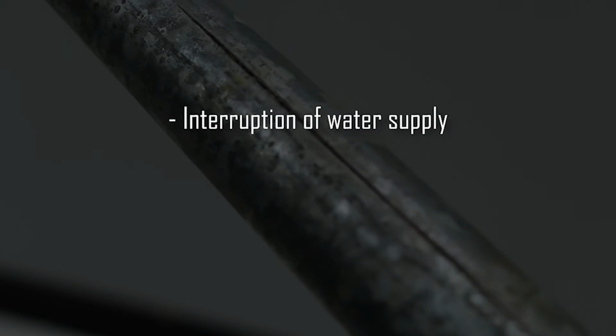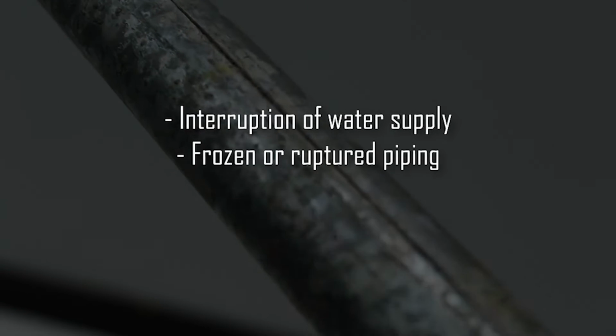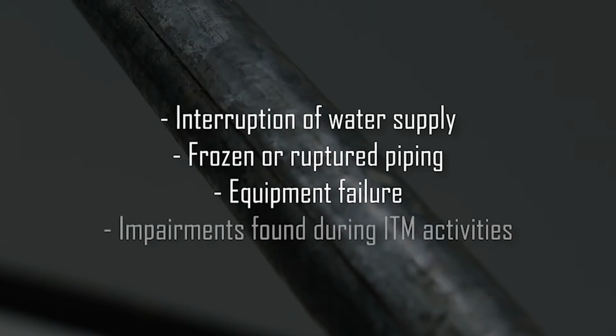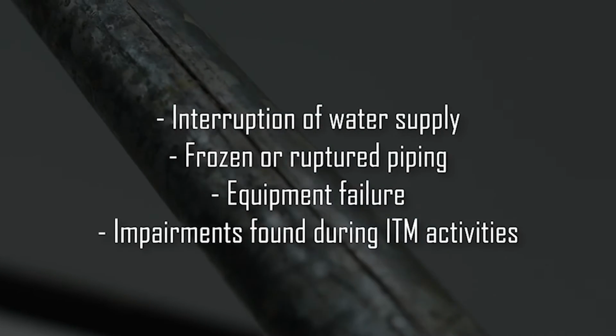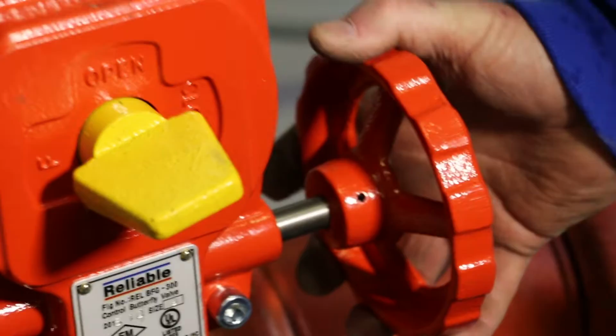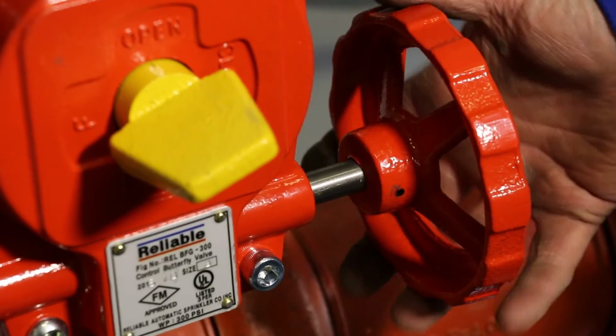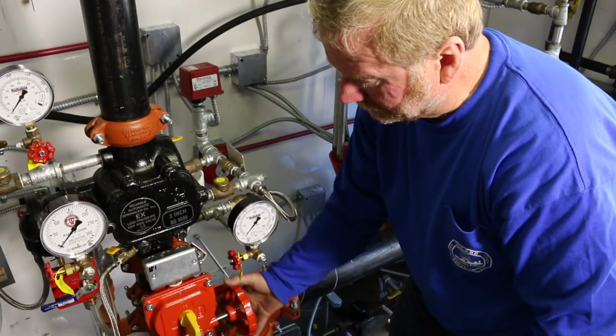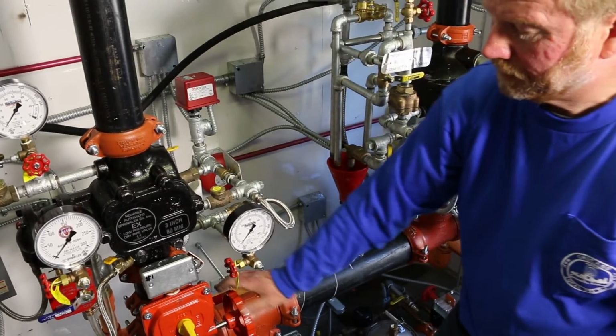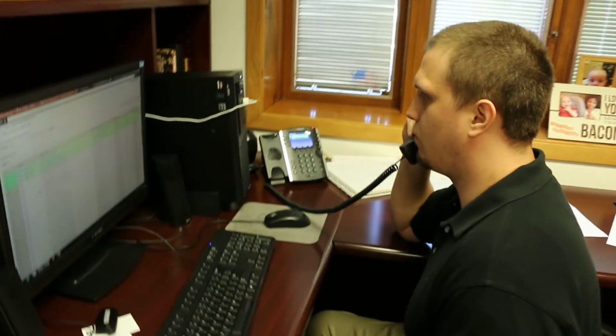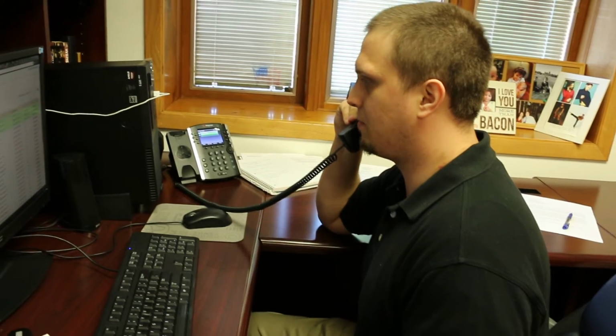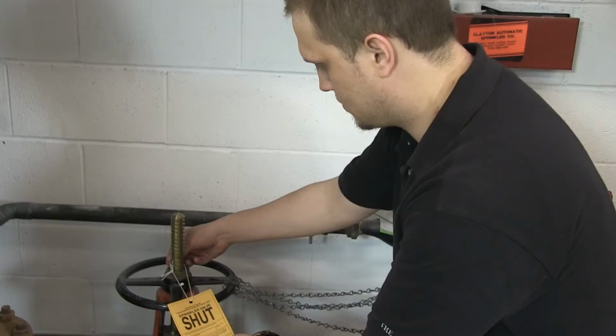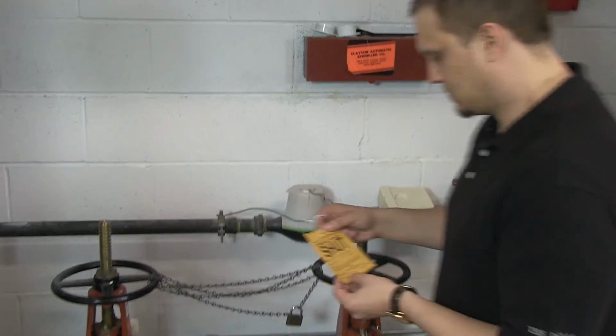Emergency impairments include, but are not limited to, interruption of water supply, frozen or ruptured piping, and equipment failure, as well as impairments found during ITM activities. When all impaired equipment is restored to normal working order, the impairment coordinator must verify that all inspections and tests have been conducted to ensure affected systems are operational. All those who were alerted that the system was impaired must be notified that it has been restored and the impairment tag has been removed.